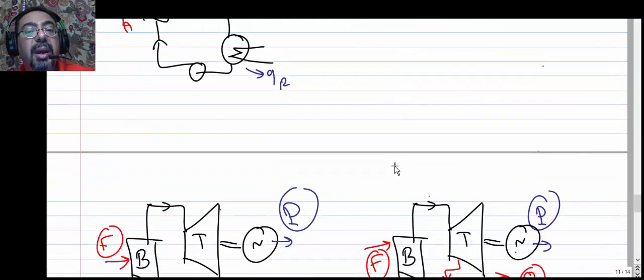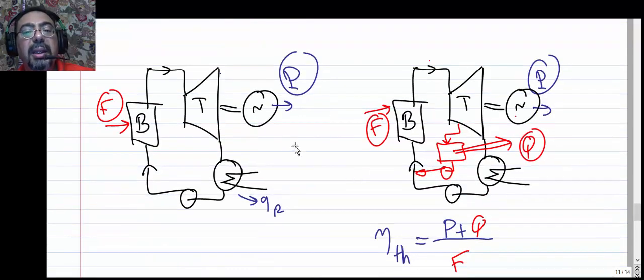But now when we have combined heat and power production, rather than just having output electric energy coming out, you will get some of the steam in this Rankine cycle and have a heat exchanger, and you will get Q. Whatever the method to extract that energy, it's the gas turbine, and you get the power, and you get some Q in the exhaust, in the heat recovery boiler that will be sitting in the exhaust. The point is you have two outputs now, P and Q. And you are paying fuel in the boiler to generate this and this.